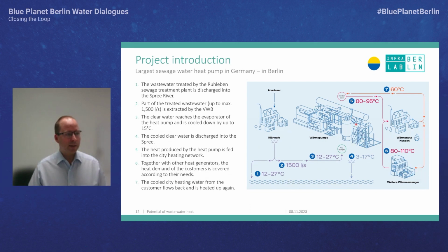What we do then is push the heat up to a higher temperature level, put it into our district heating system, which will be around 80 degrees C during summertime and 95 degrees C in wintertime. Then it gets mixed with other heating facilities and distributed to our customers, who cool it down to around 60 degrees C, and then the cycle of the district heating water begins again.